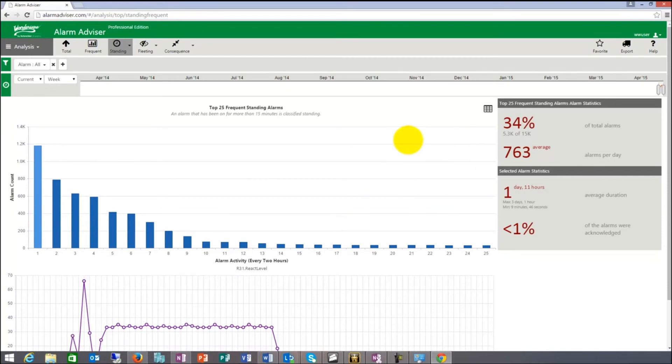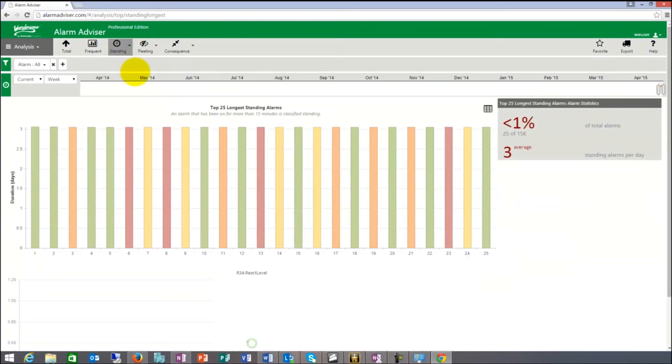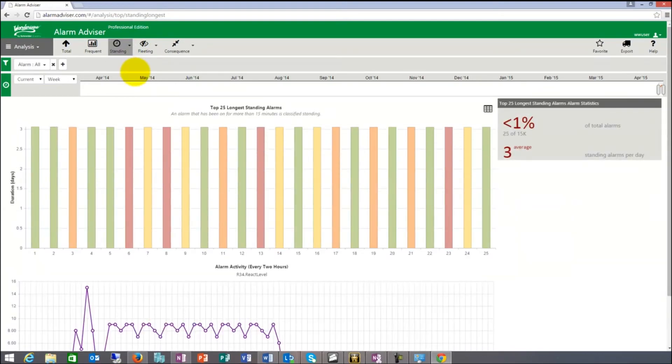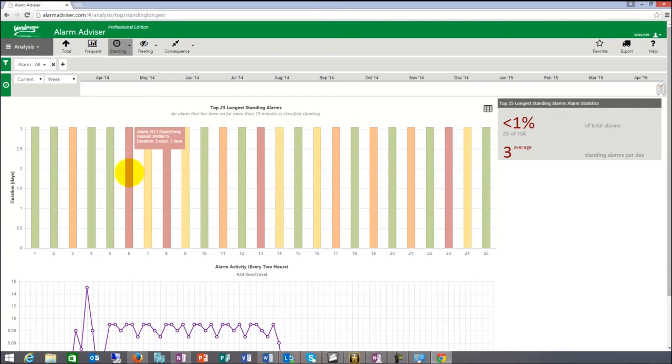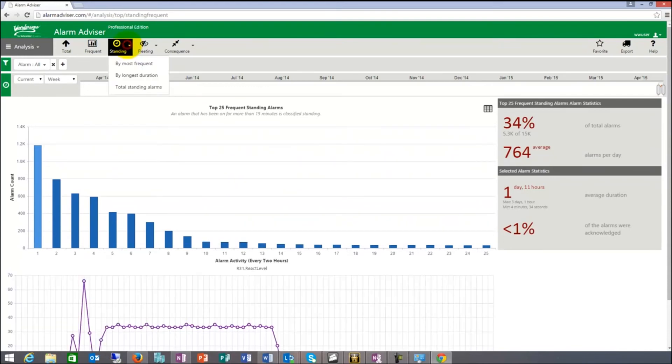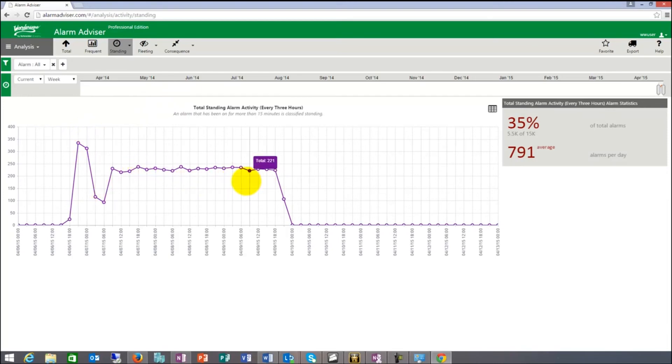We talked a little bit about how we can reduce these. There are two reports here, by most frequent, things that happen more often, or standing alarms that basically are indicated by longest standing alarms. This one was on for three days and four hours. And the color indicates what severity it is. Here's a critical alarm that was on for three days and one hour. That's based on frequency, standing by most frequent and the longest. And then the total of standing alarms, which will give you the total counts, which is the one in the bottom. And you can see by time, at what time of the day, week, month, year, you had the largest amount of standing alarms.